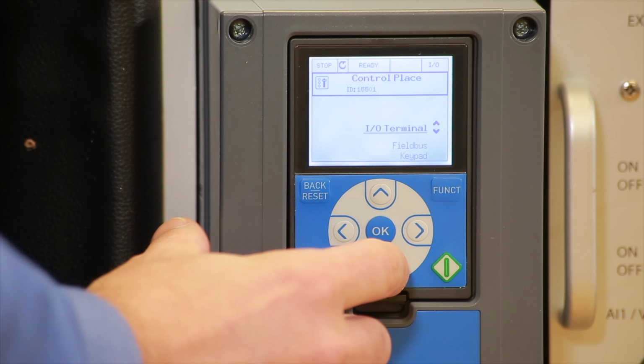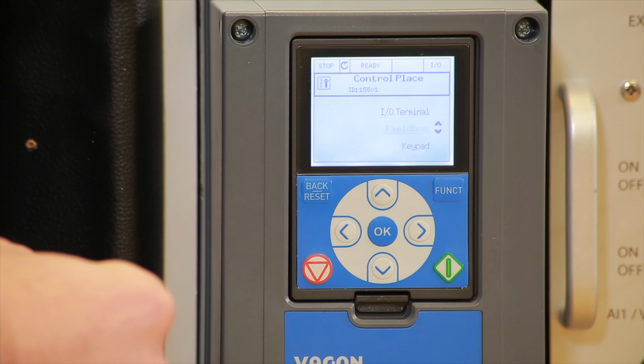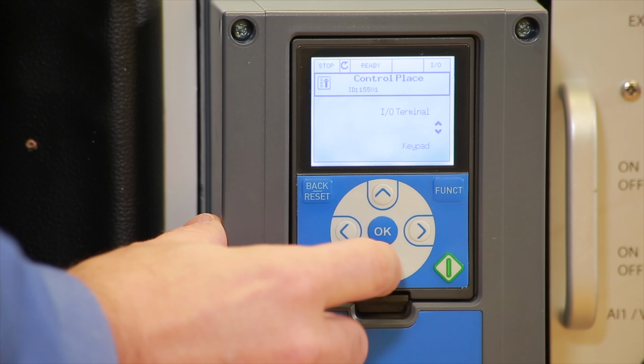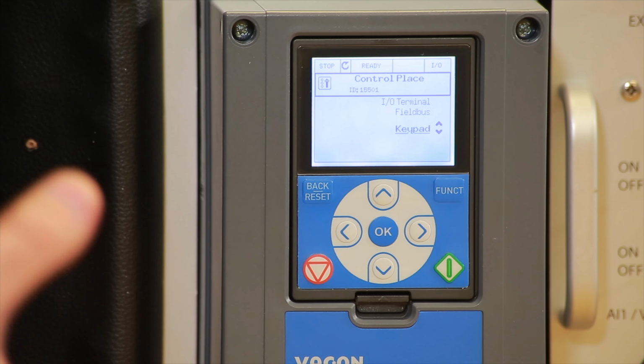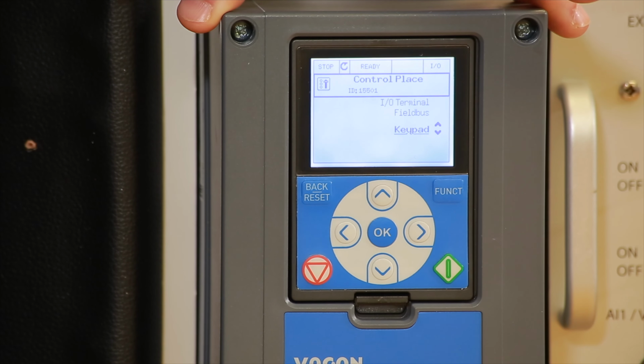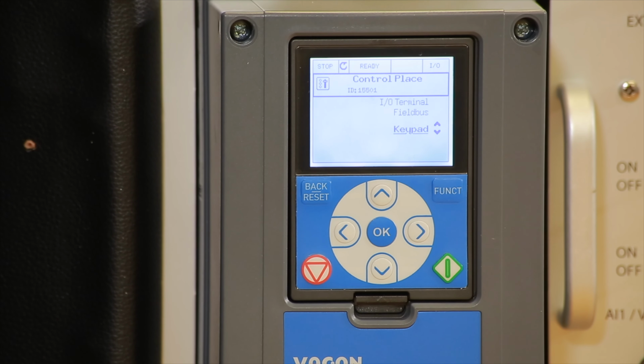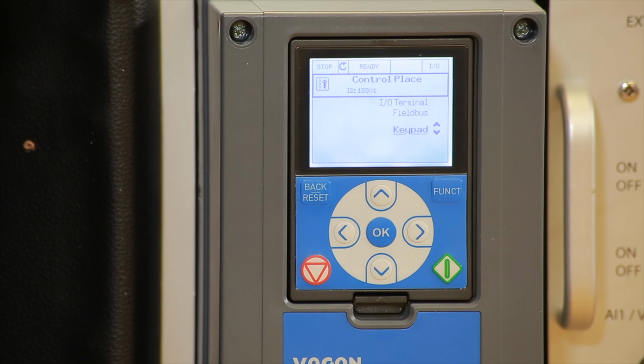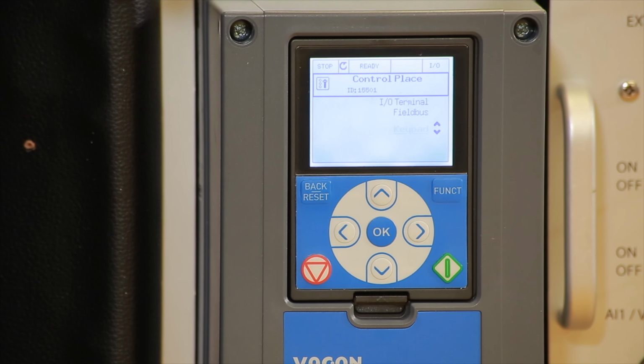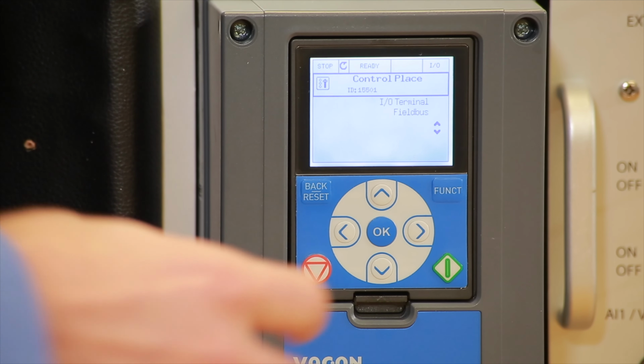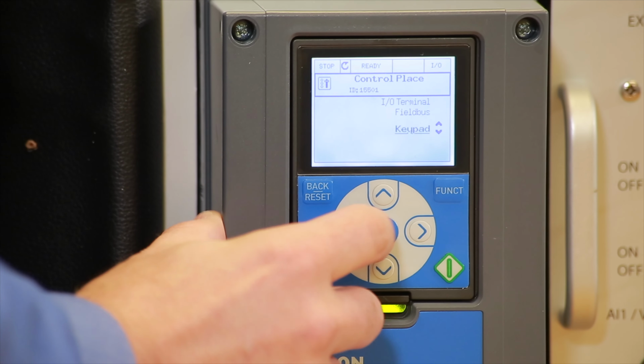Input-output terminal is the selector switches. Fieldbus would be your Ethernet or Modbus TCP, and or keypad. So right now we want to demonstrate how the drive runs standalone. Therefore we're going to select keypad because we do not want to operate any selector switches. We want everything to be standalone, a drive on a wall. Very simple. So we'll put keypad.